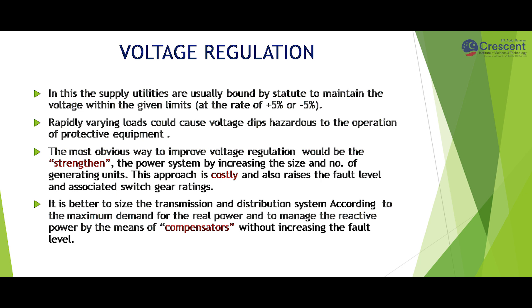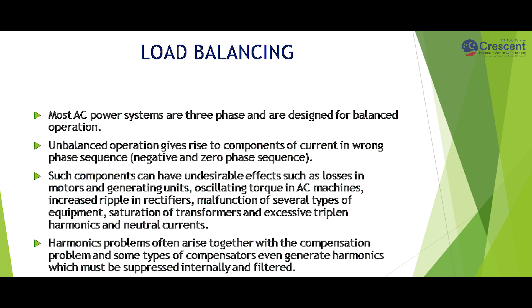The obvious way to improve voltage regulation would be to strengthen the power system by increasing the size and number of generating units, but this approach is very costly and raises the fault level and associated switchgear ratings. The better option is to size the transmission and distribution system for maximum real power demand and manage reactive power using compensators, without increasing the fault level.